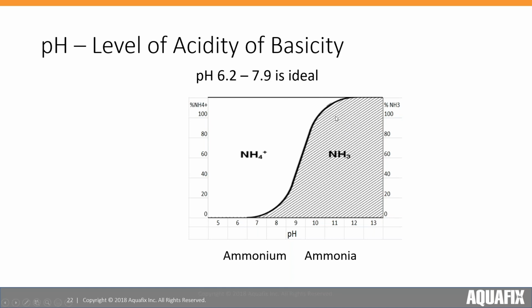But ammonia at lower levels is toxic, and that still really depends on what your pH level is. So when a plant gets a high pH, above 8.5, there starts to be some real large inhibitory effects just from the ammonia. Most plants, except in industrial applications, will typically not have to deal with this high pH, since it's more common for wastewater treatment plants to be right around 7. Municipal plants that do tend to struggle with pH generally end up with more problems on the low end.